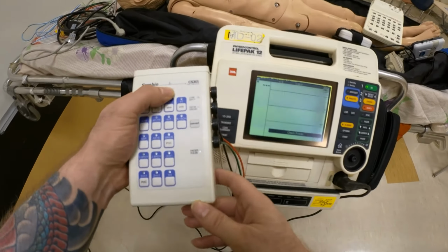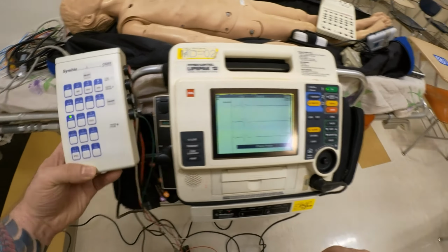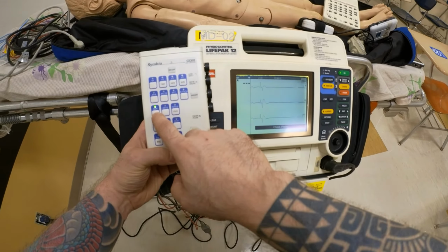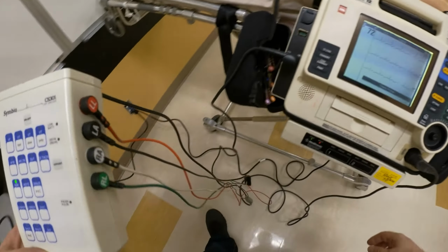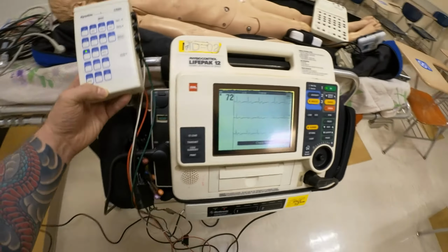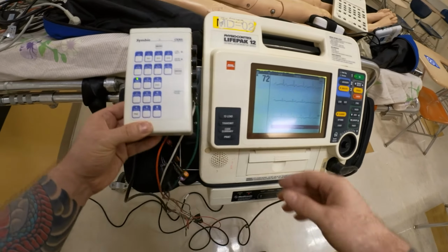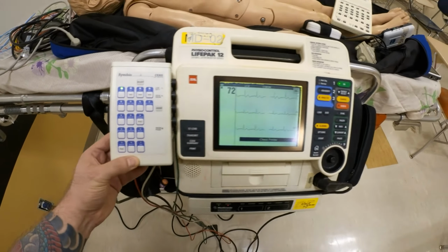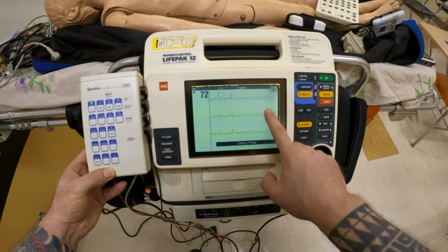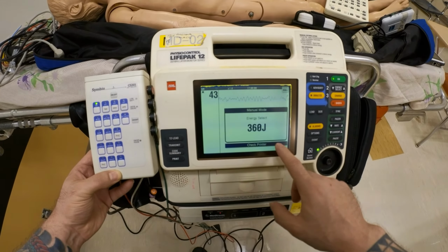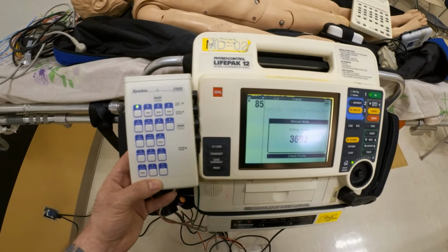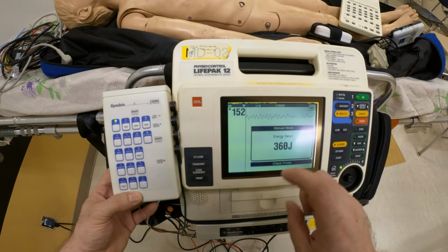So when it's connected, you turn this on, and it's right away normal sinus rhythm, and you see the rhythm appearing. Because it's connected to the pads and leads, you could perform all your electrical therapy. So if we put in ventricular fibrillation, you'll see the conversion. You could essentially have it be able to defibrillate. This will accept 360 joules for the shock.